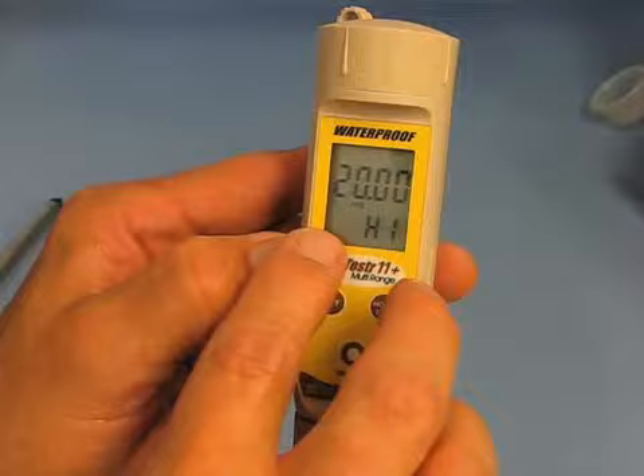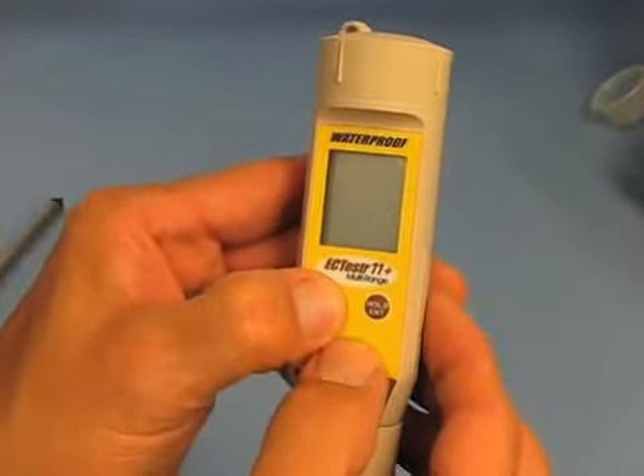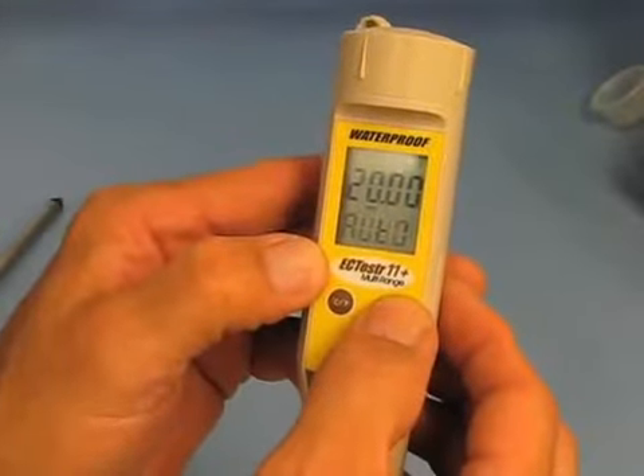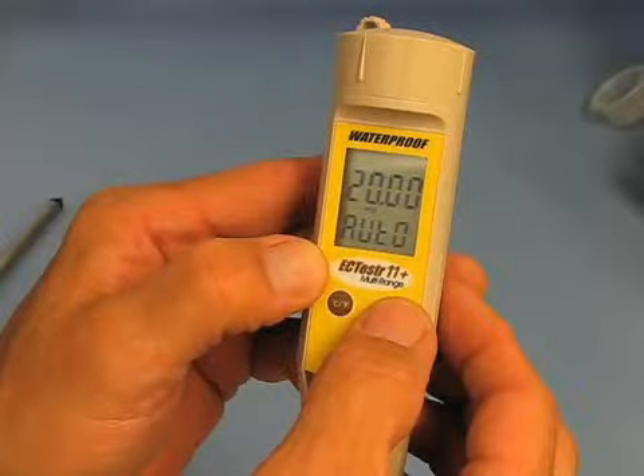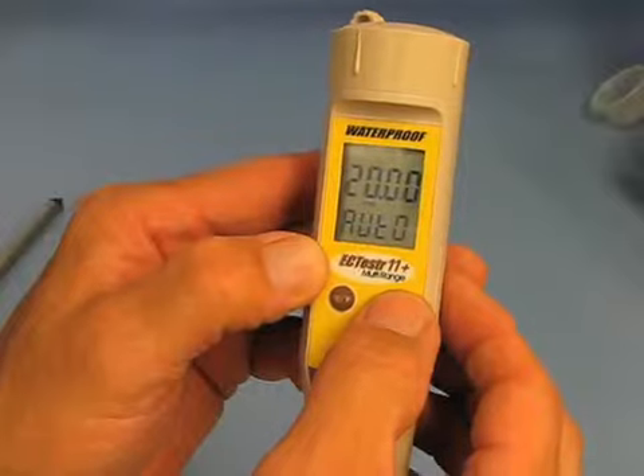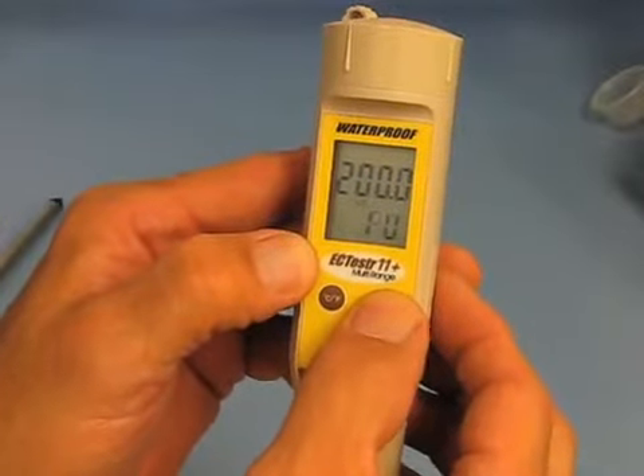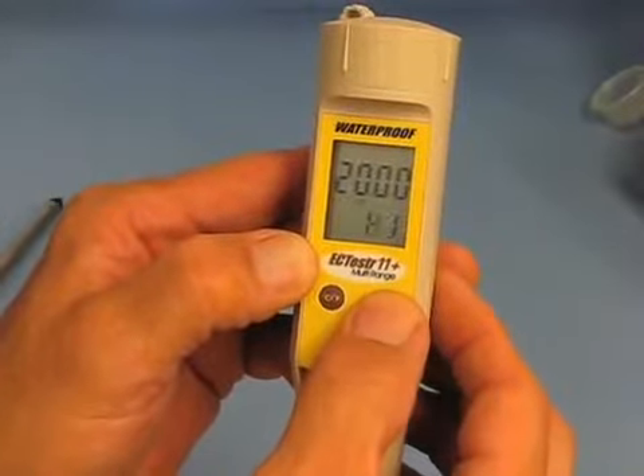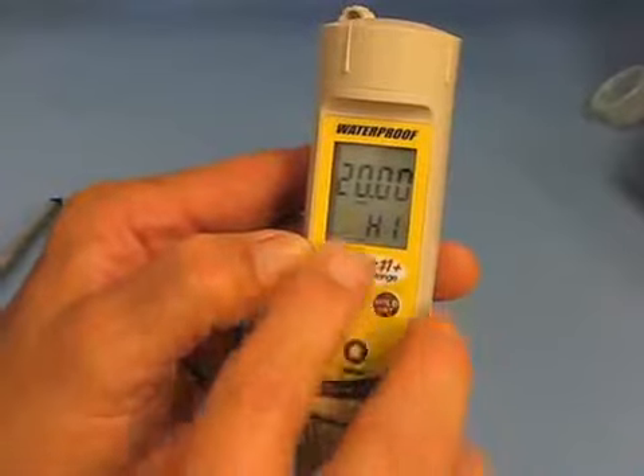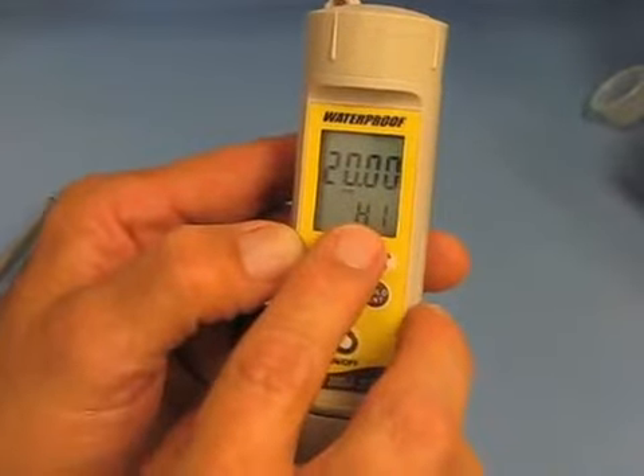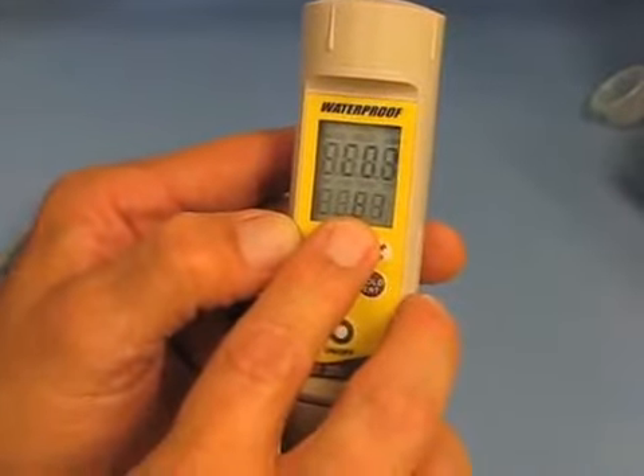To adjust the range, press and hold the temperature key and then press the on-off button. Release those keys and then press the hold enter key to cycle through the options for range. The options for range will be displayed: auto, PU, low, and the high range which you're looking for. It'll cycle through those and it will automatically put you back into measure mode after you're done.